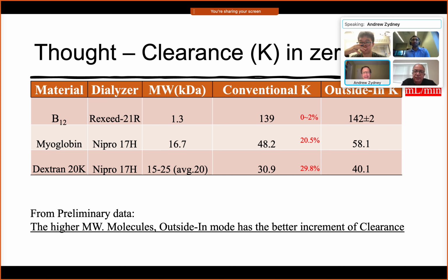And so, like I say, it's hard to move that point unless you're going to redesign the dialyzer in some way. Using various restrictions, we think we can move that point somewhat. Would that be desirable? Like I say, if you were trying to exploit this to increase the clearance, I could see a point for doing that. But I think once you put the size selective layer on the outside, this effect is largely going to go away.